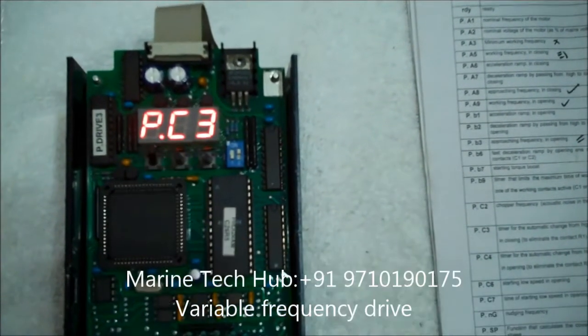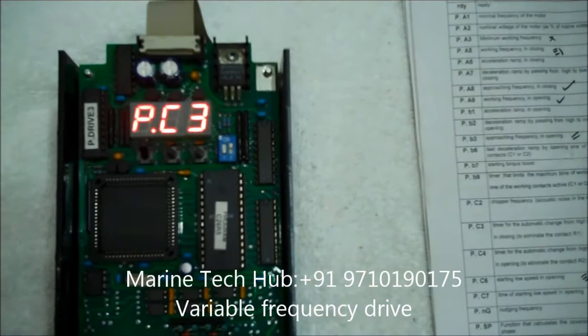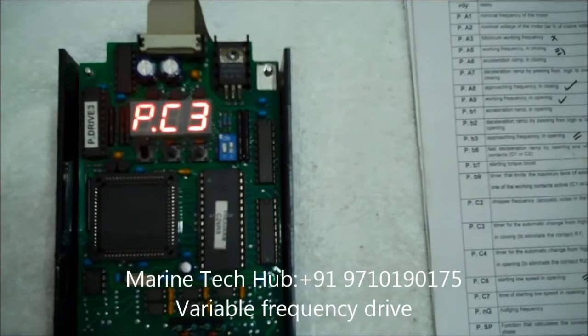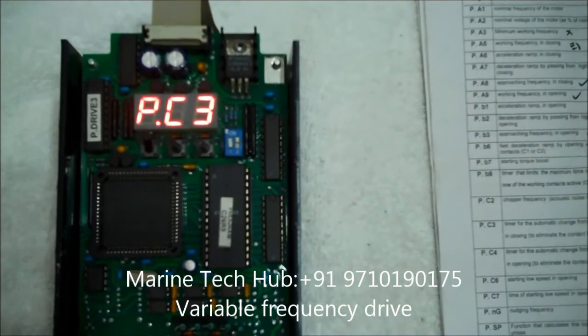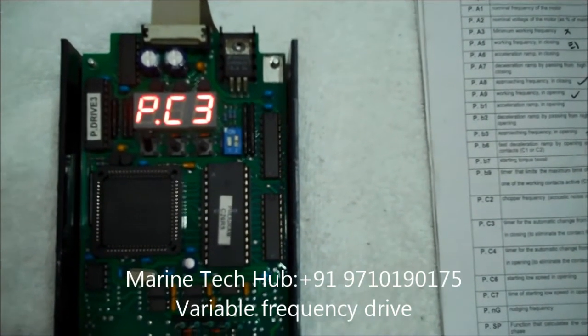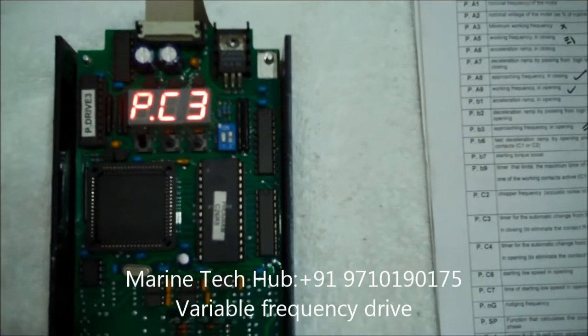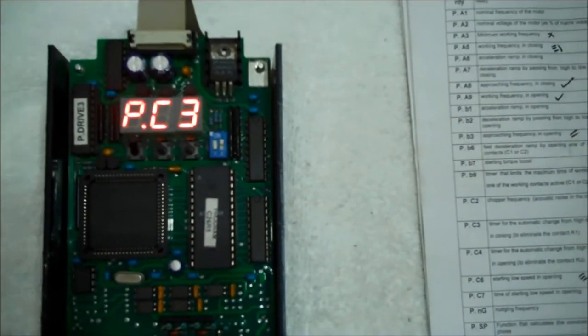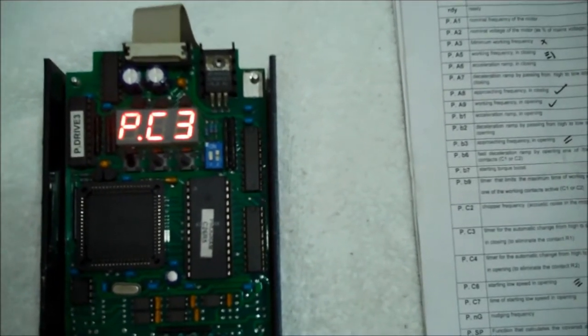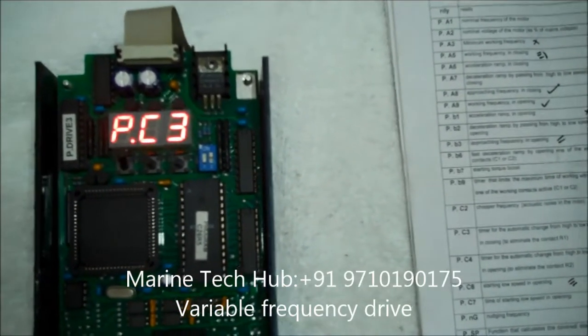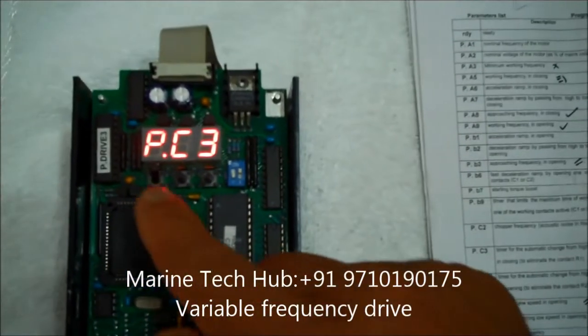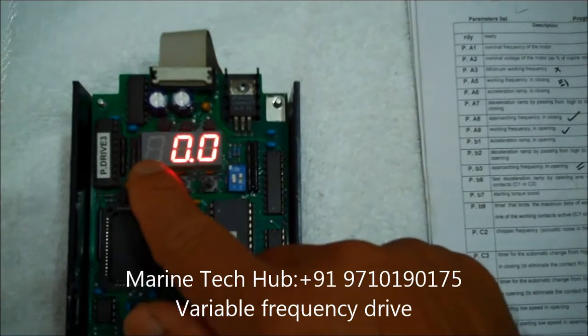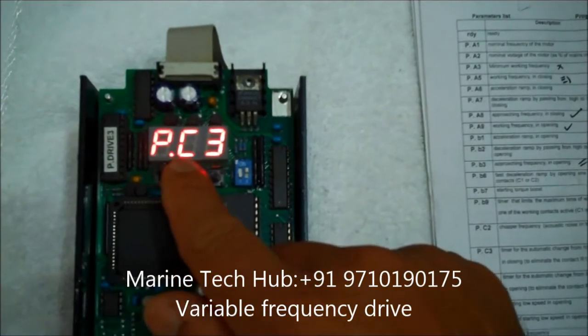Next I will go to the next PC3. This is the timer for the automatic change from high to low speed in closing. This is normally kept 0 here. So it is 0. Okay.